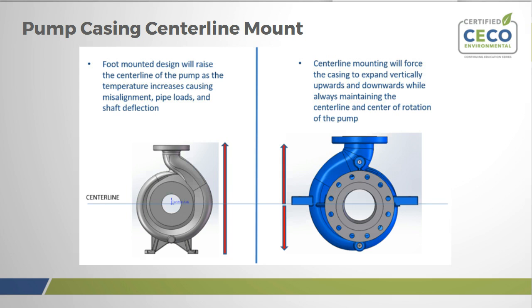In this case, as the temperature increases at a pump such as this, the center line of the pump will stay the same because it is at the base of the pump. The pump is going to grow from its base, which is now at the center line. So the bottom half of the pump will grow downwards. The upper half of the pump will expand upwards. But the center line of the pump will stay exactly where it's supposed to be. And thus keeping the impeller, the shaft, and all the high-speed rotating components located right where they're supposed to be in the center of the pump.